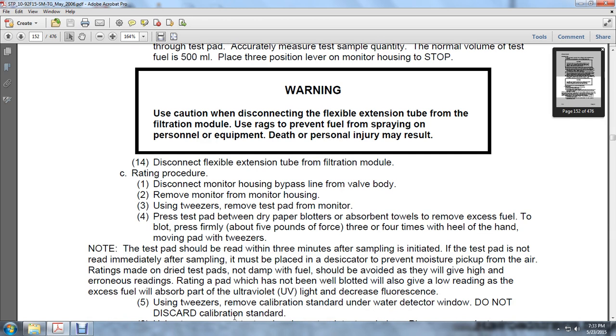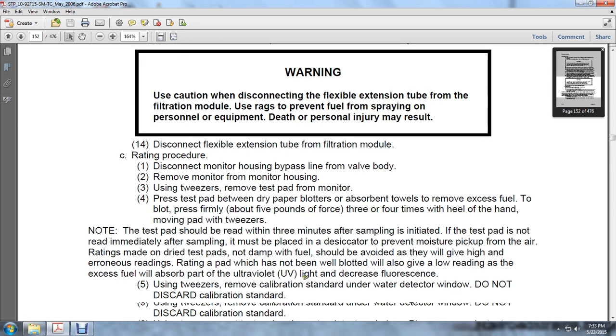Note: the test pad should be read within 3 minutes after the sampling is initiated. If the test pad is not read immediately after sampling, it must be placed in a desiccator to prevent moisture from being picked up from the air. Ratings should be based on a dry test pad. A pad damp with fuel should be avoided as well, since it will give a high reading. Rating with a pad which has not been well blotted will also give a low reading, as excessive fuel will absorb part of the ultraviolet light and decrease the fluorescence.